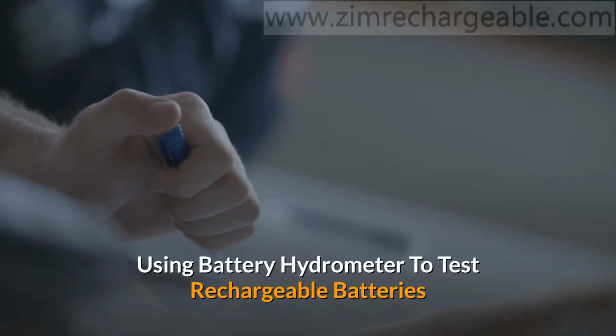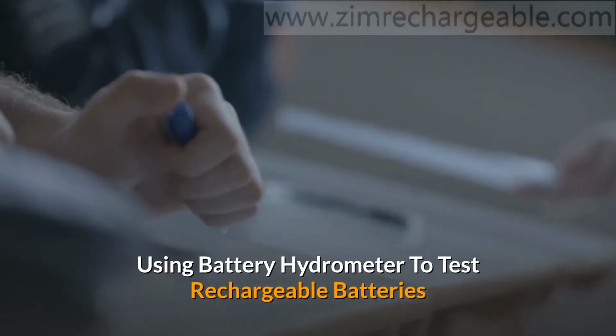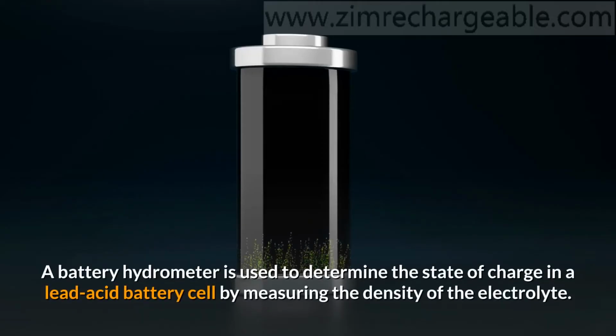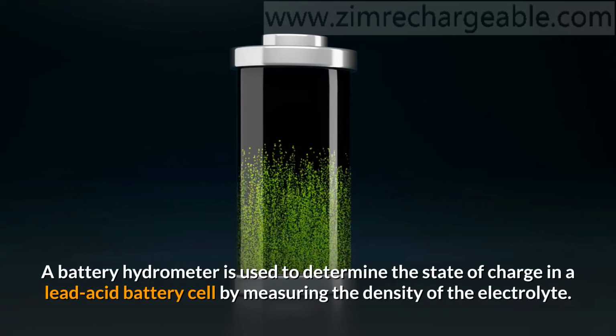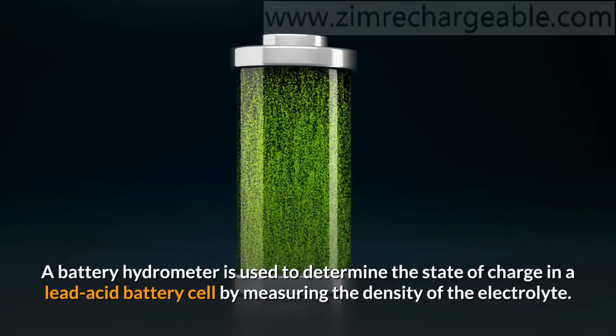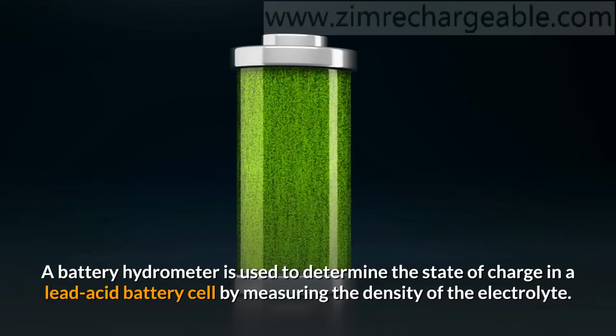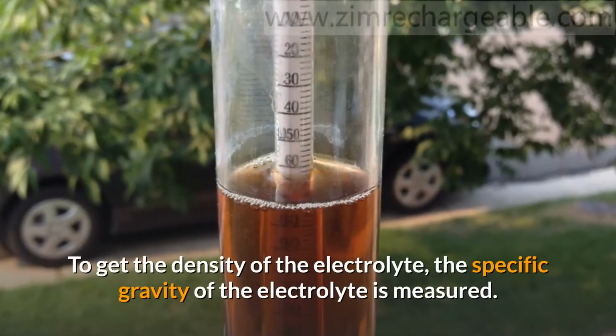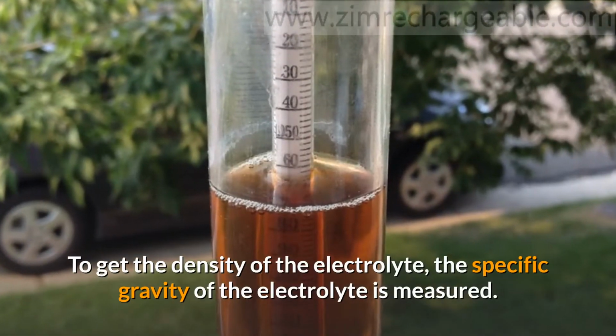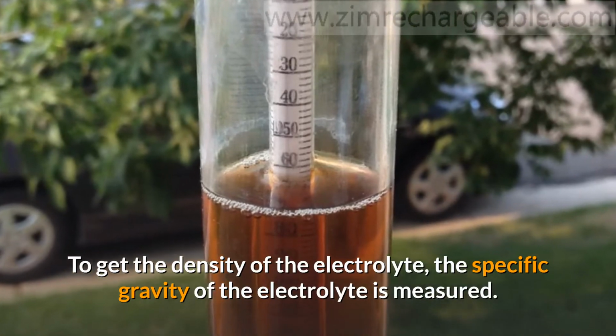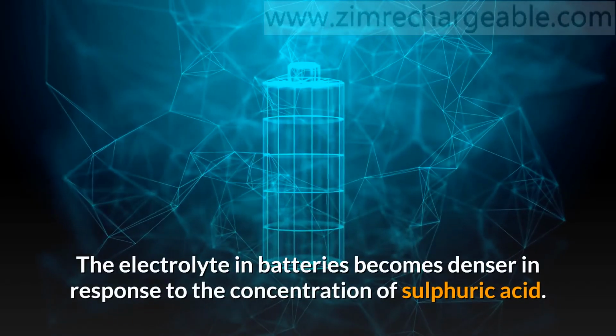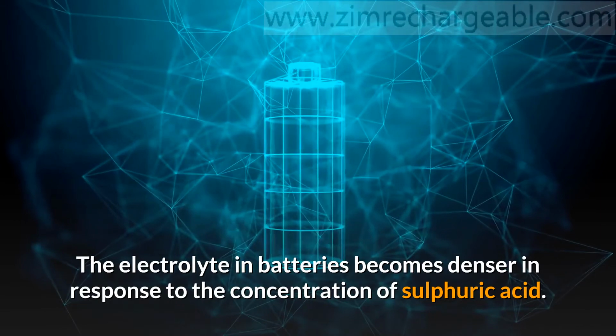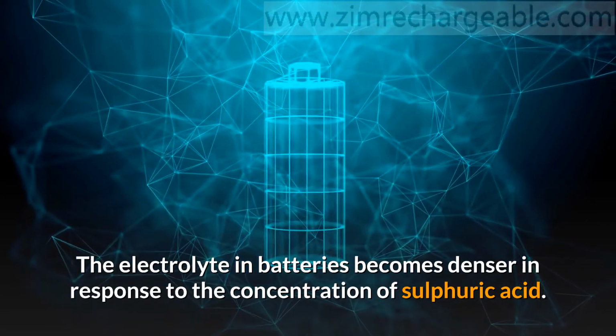Using a battery hydrometer to test rechargeable batteries. A battery hydrometer is used to determine the state of charge in a lead-acid battery cell by measuring the density of the electrolyte. To get the density of the electrolyte, the specific gravity of the electrolyte is measured. The electrolyte in batteries becomes denser in response to the concentration of sulfuric acid.